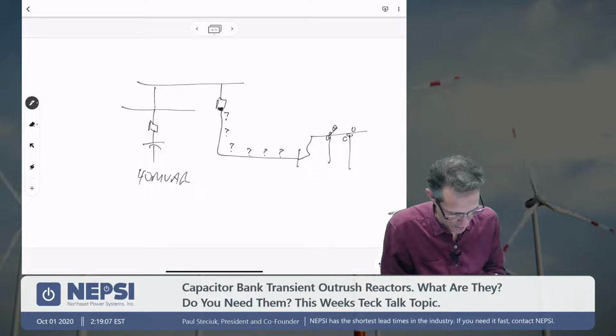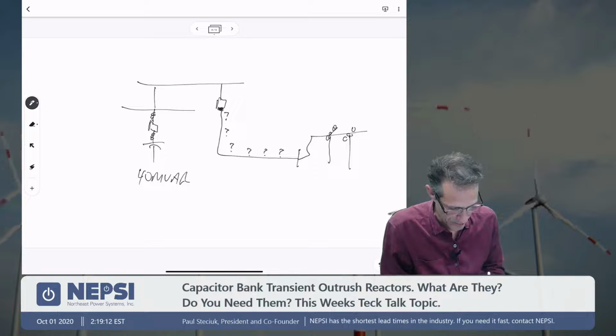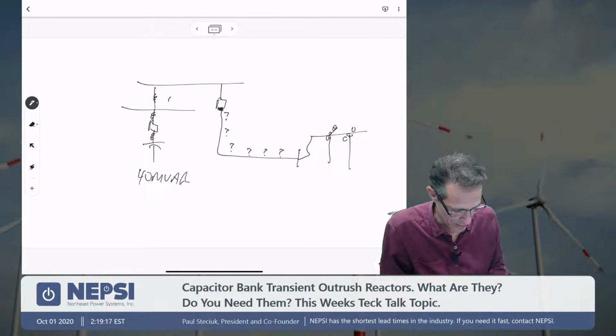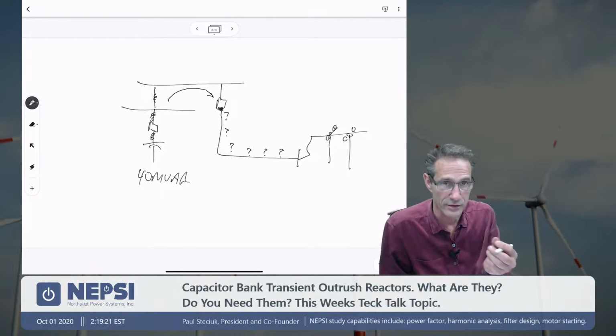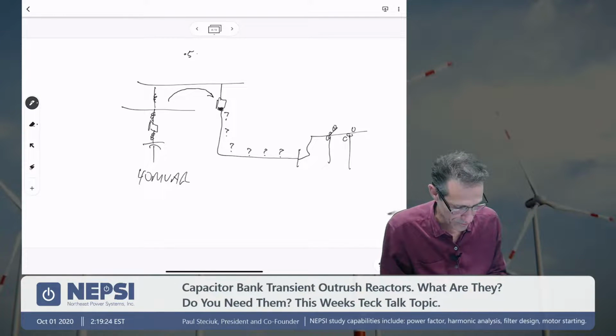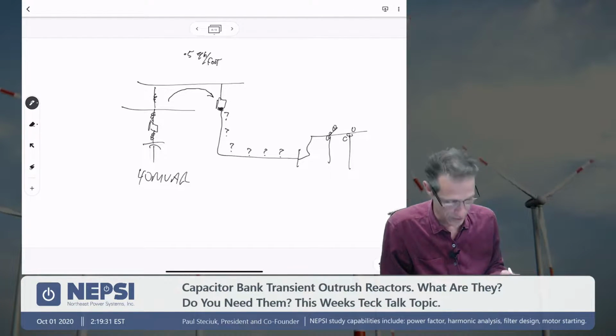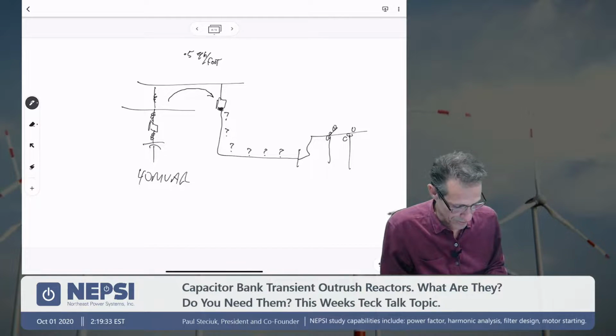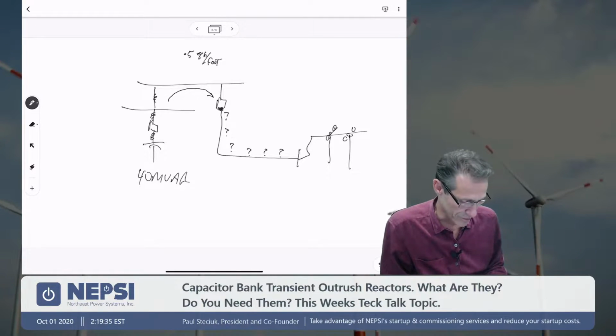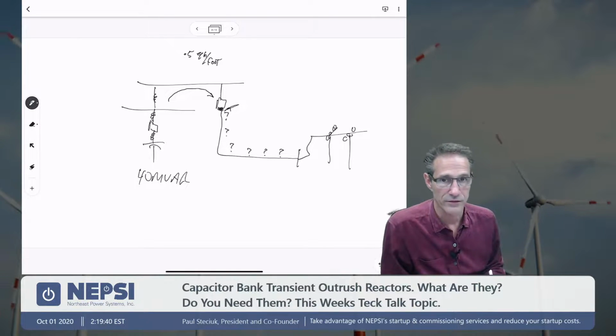That means the inductance would be the inductance inside the capacitor bank itself, plus the outrush reactor, plus the impedance of the cable, and then the distance to the actual breaker itself. We would typically use about 0.5 microhenries per foot as the value of inductance to consider. But if you have a fault inside the breaker, the breaker has failed. So in my opinion, that's not a valid location for a fault.